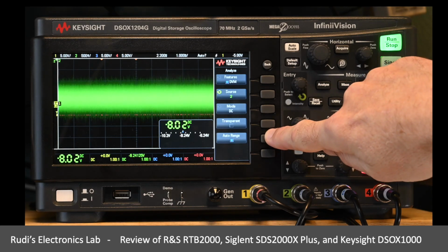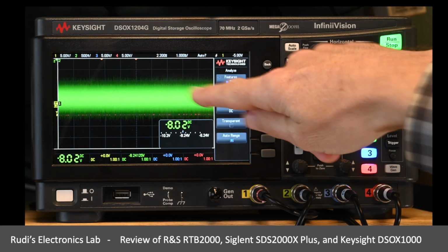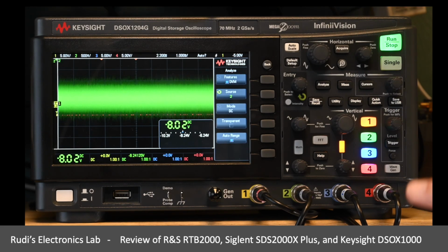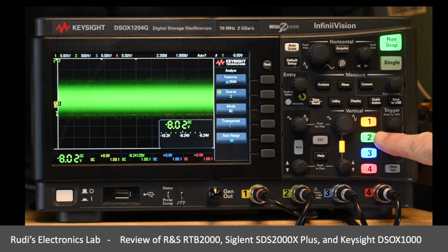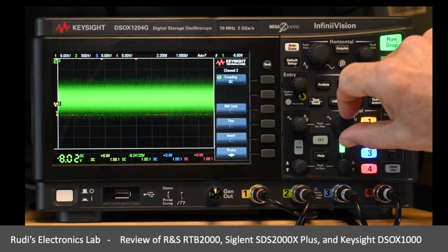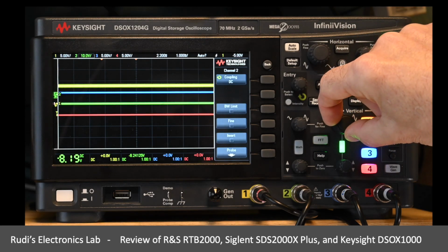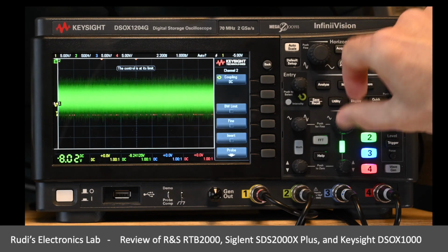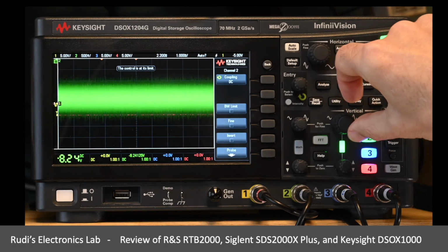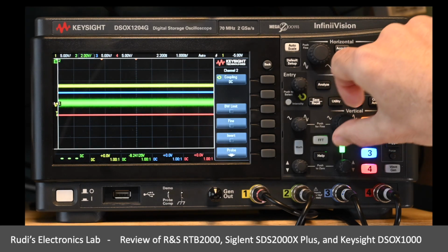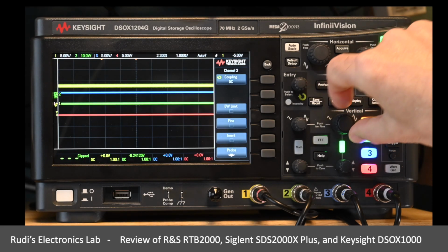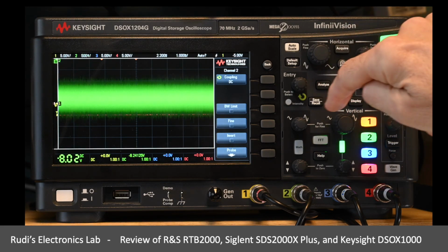We can turn it on, and actually we see now turning it to maximum sensitivity, but this overrides the channel setting. So if you selected any channel setting for that particular menu, then you have to be aware, and this is now for the second green channel. I'll just be turning it back now. You see, and I cannot even turn it back because every time I try to change the setting it is being overridden by that automatic range setting.